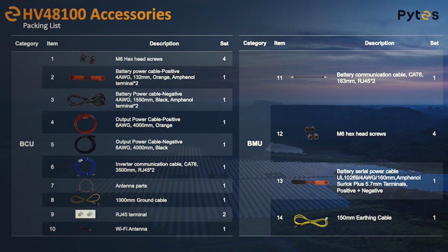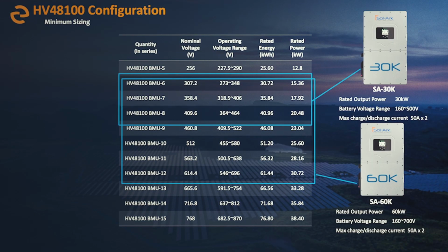Depending on what inverter you might be using, especially when we look at Sol-Ark's commercial offerings, right? They've got a 30K and a 60K. The voltage input ranges on both of those units is a little bit different. The 30K has a 500 volt input limit, meaning we can't connect any more than 8 modules in series. So if somebody needs more than 40 kilowatt hours, you've just got to create another stack. The 60K Sol-Ark, on the other hand, has a higher voltage input of 700 volts, so we can do up to 12 in series on the 60K without any issues.